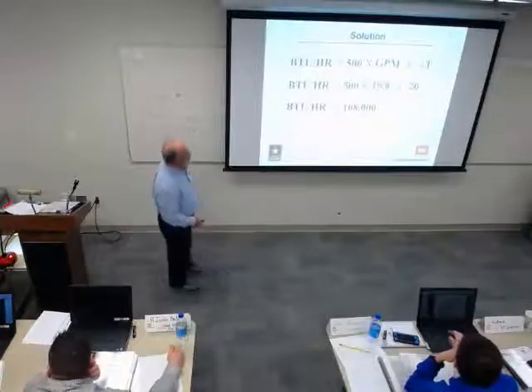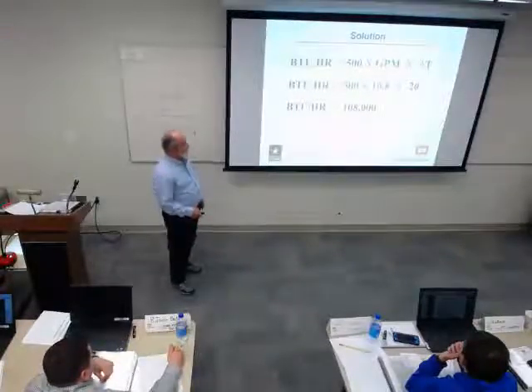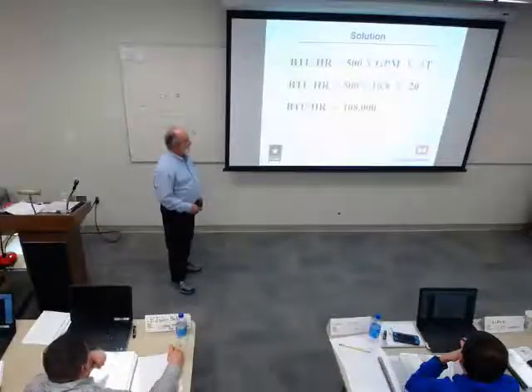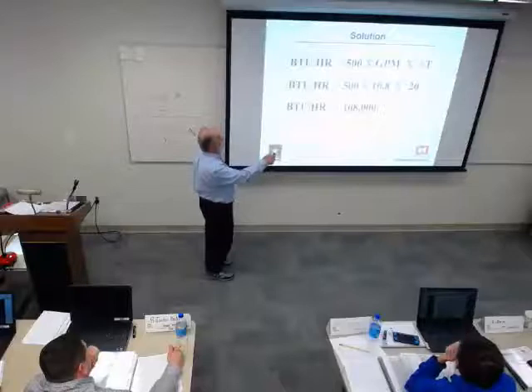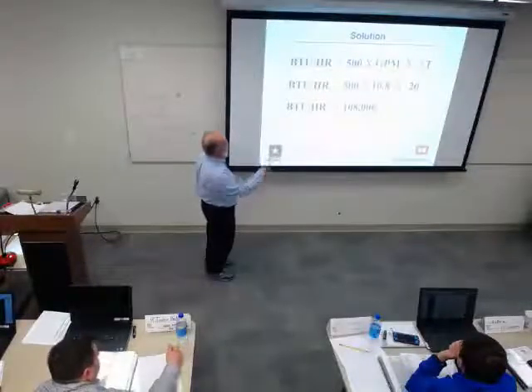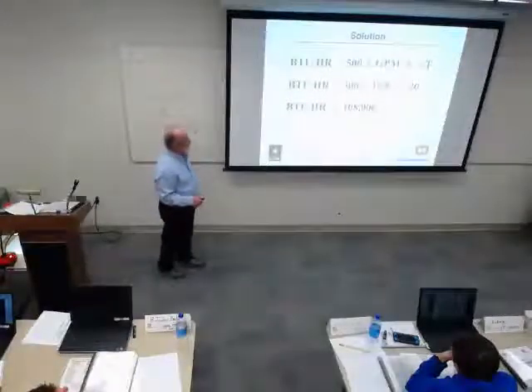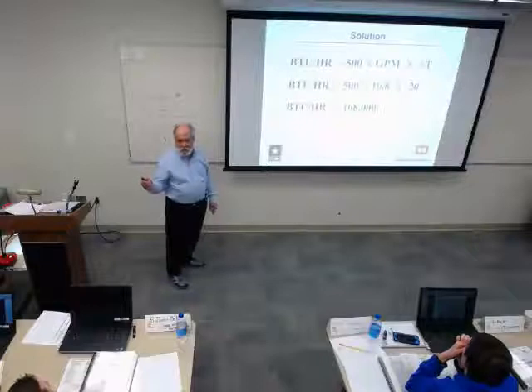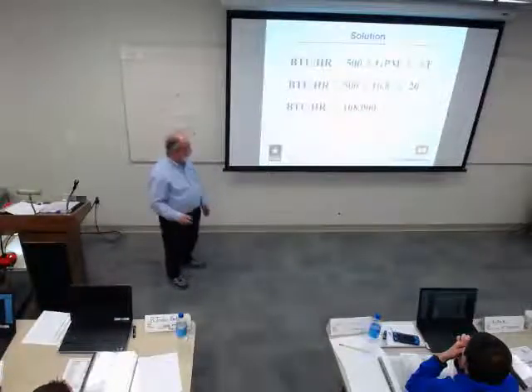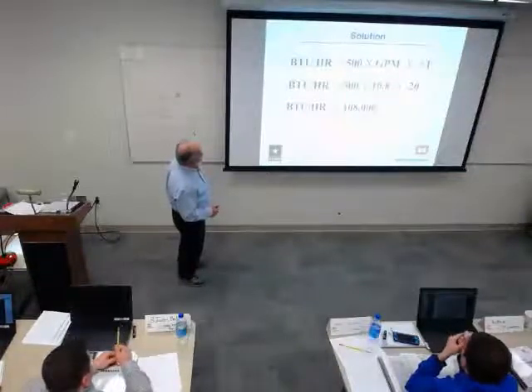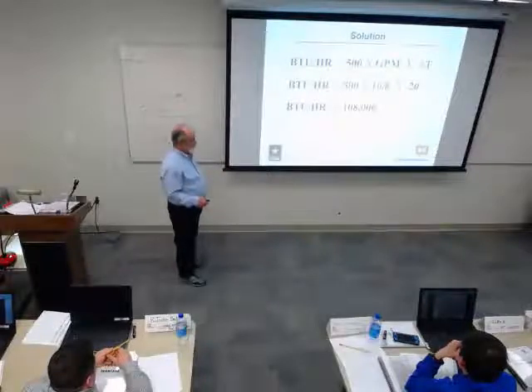BTUs per hour for the water side is 500 times the gallons per minute times the change in temperature. And that 500 contains quite a few things. It converts hours and minutes, because of gallons per minute to BTUs per hour. And then it also has density in there, and I think the specific heat, which is 1, is what they're using. So 500 times gallons per minute times the change in temperature gives us our BTUs per hour. And remember, with a BTU you can raise a pound of water 1 degree. So we got 500 of those. So there we go. Our BTUs per hour on this now are going to be 1,000 or 108,000. We plugged our numbers in up there, and that's what we got.